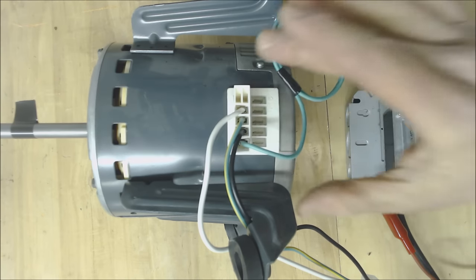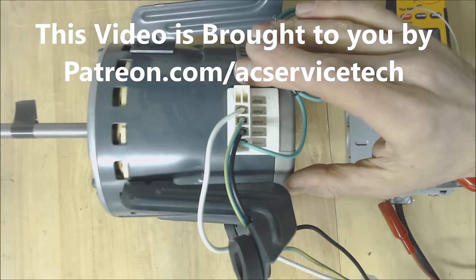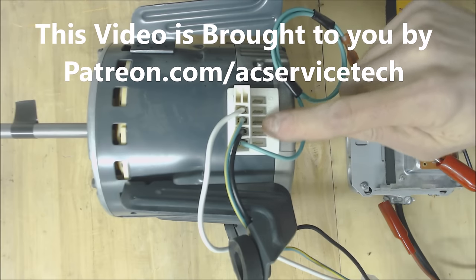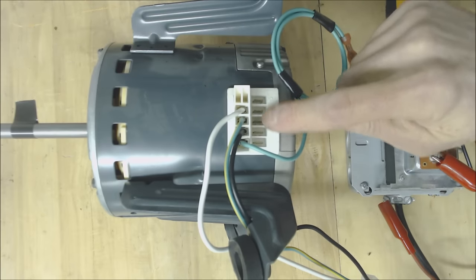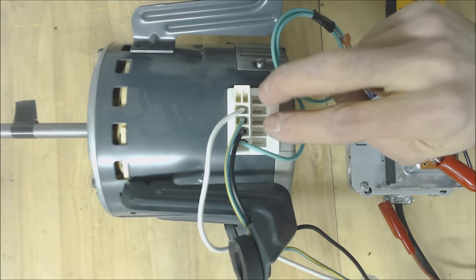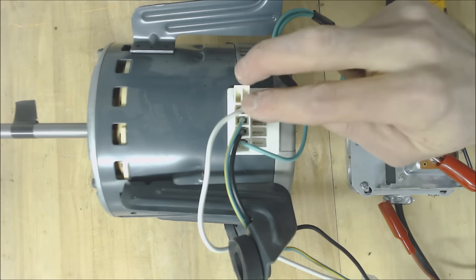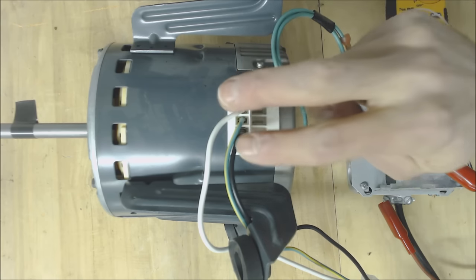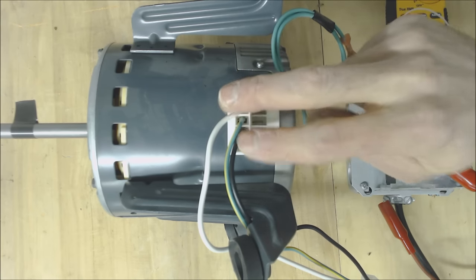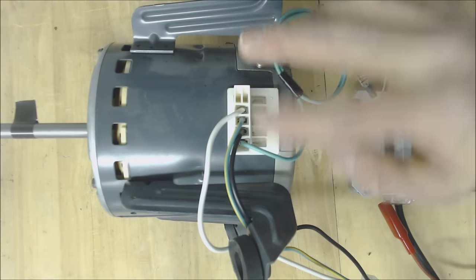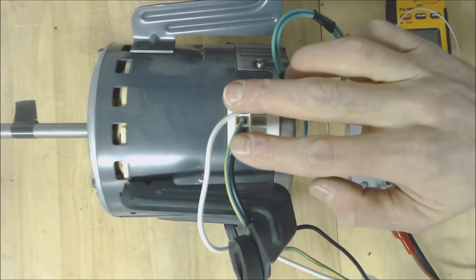This is an ECM blower motor and this one actually has 24 volt signals right here from 1 through 5 and this is powered all the time with 120 volts or other models are powered with 240 volts right here.